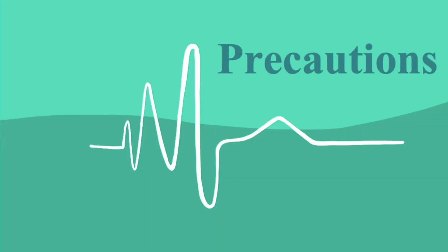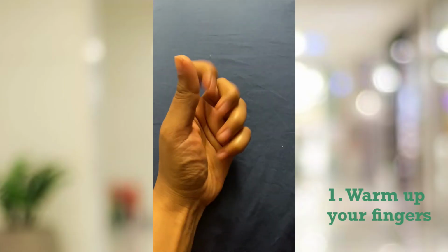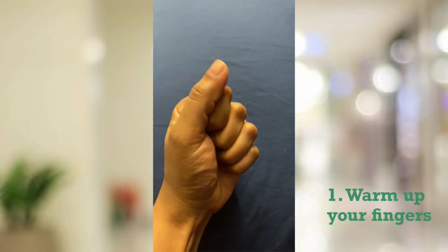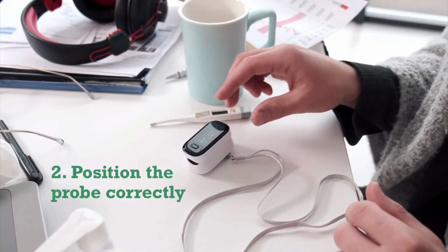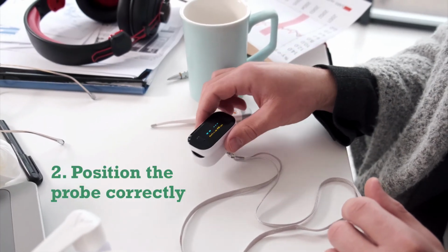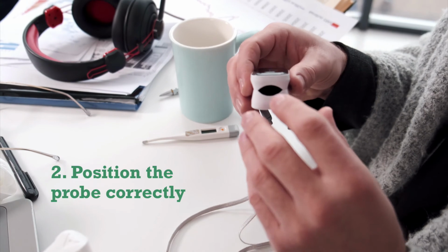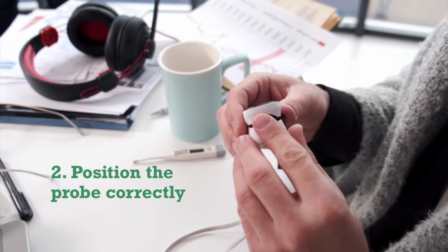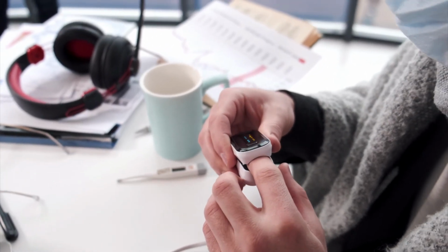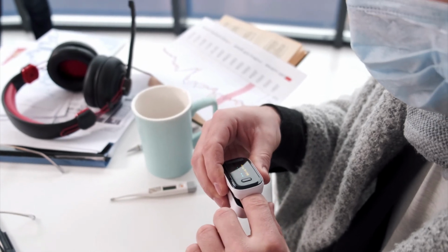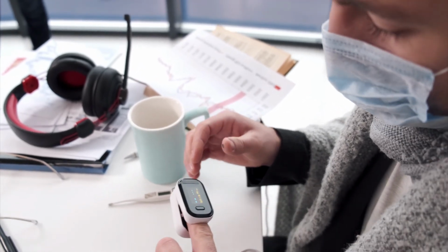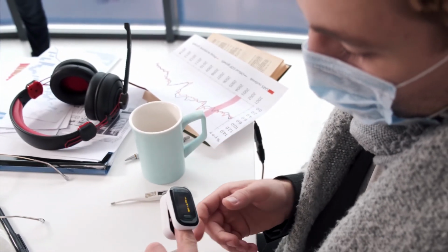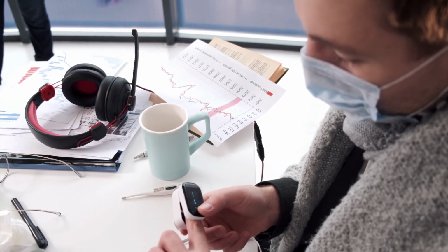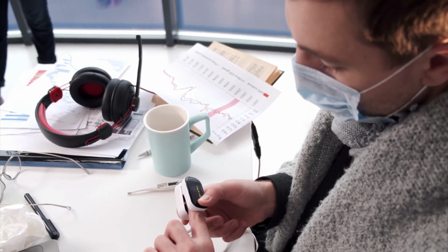Now, what are the precautions one should take before using the oximeter? First, warm up your fingers before placing them in the device. Second, position the probe correctly. Make sure you are sitting still or in a stable position for the reading, because the patient's movement can affect the reading. Positioning should be appropriate: it should not be too tight, so that it does not constrict blood circulation. It should not be too loose.